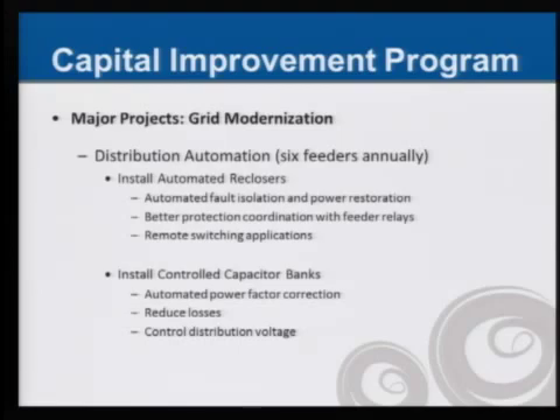Part of that project is to install automated field reclosers on our distribution feeders, which will enable us to automatically isolate outages and faults and restore power to unaffected areas. It will give us better coordination of our protection devices and remote switching capabilities. The next project is to install automated and controlled capacitor banks on our feeders, which will help with power factor improvements and corrections, reduce our losses, and help manage distribution voltage.